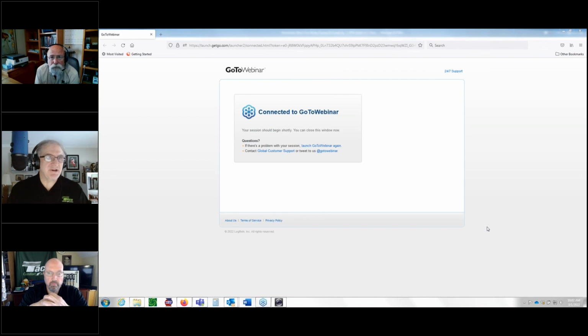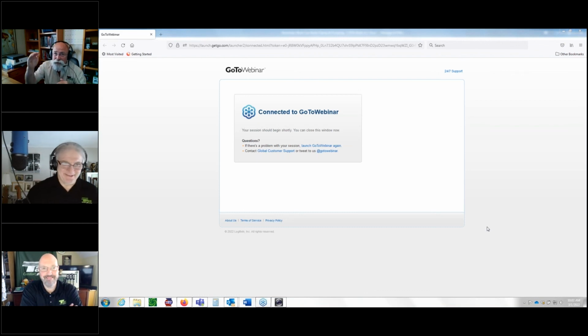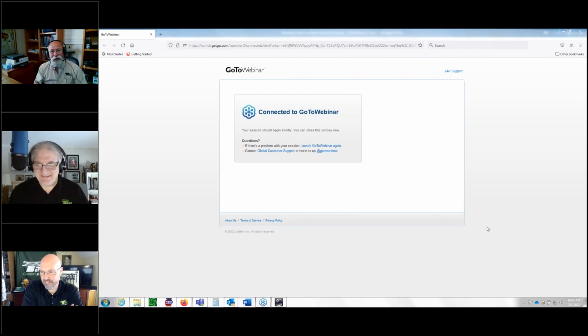So those are kind of the field options. It's never wrong to use closely spaced tees under the right circumstances, and it's never wrong to use a hydraulic separator. So it just kind of depends on what you're after, I suppose. Yeah. Another thing to remember, some of the boiler manufacturers are still making condensing equipment that are high mass. So what does that do for us? That's a big help. That reduces our cycles, and it's the only reason, like John mentioned, we're putting a buffer tank in there.